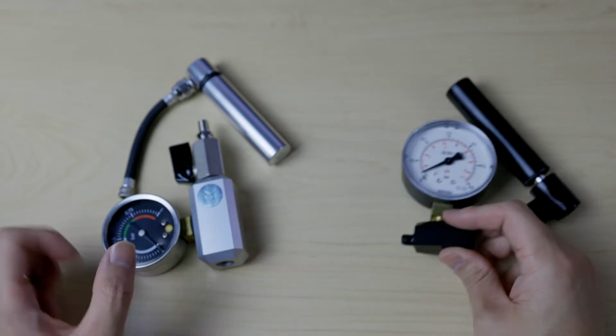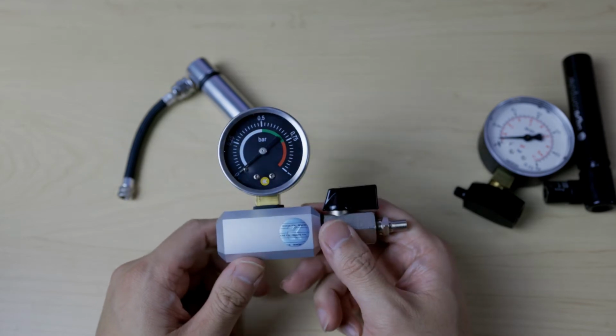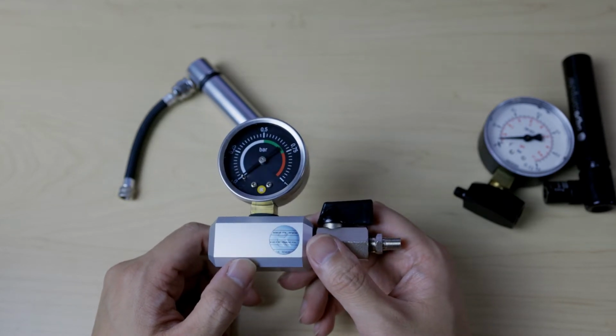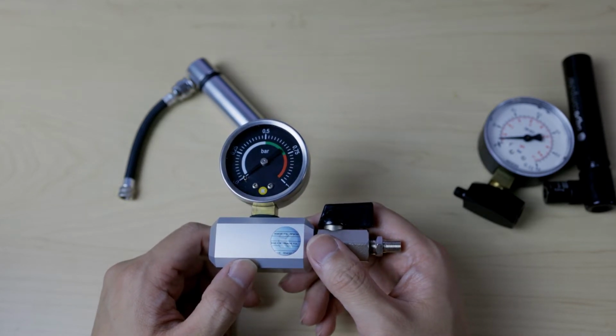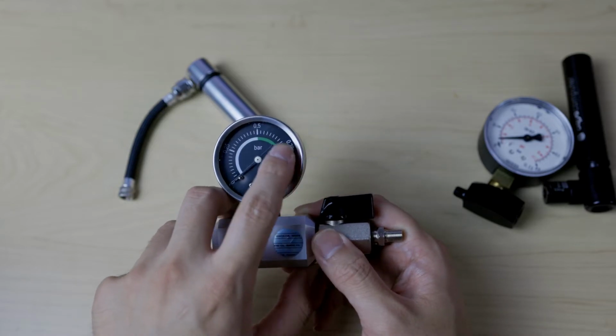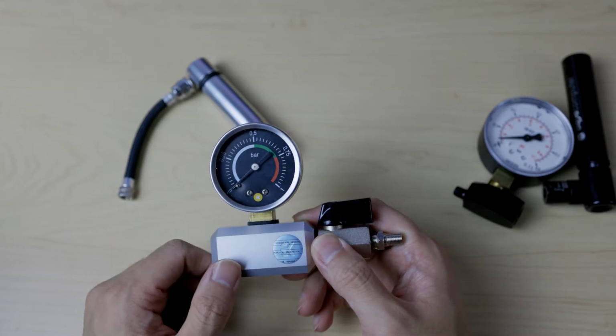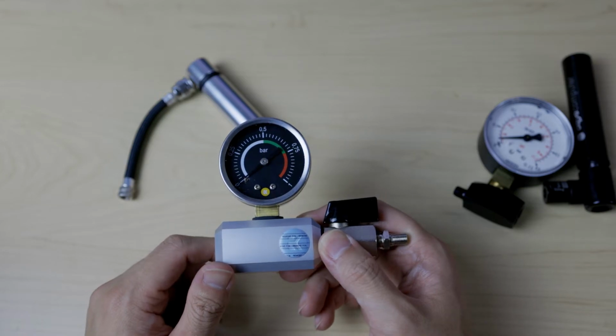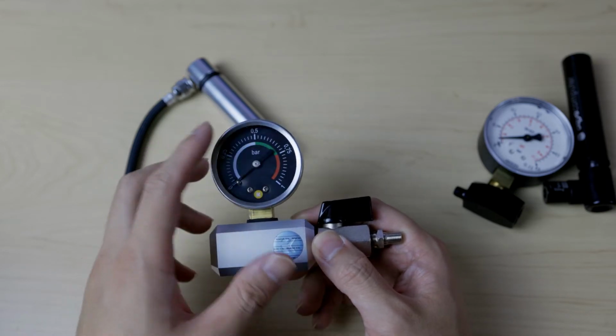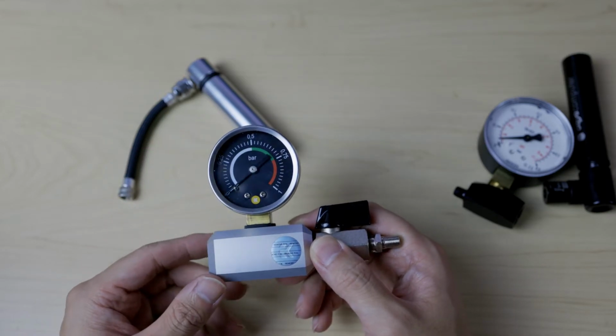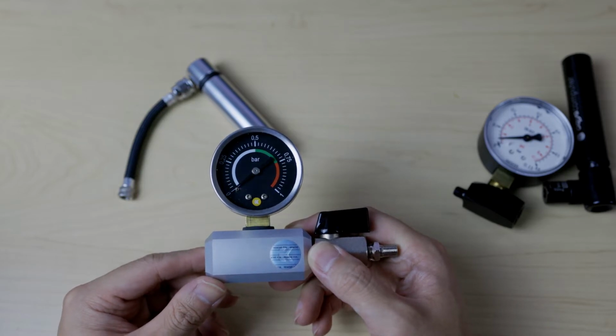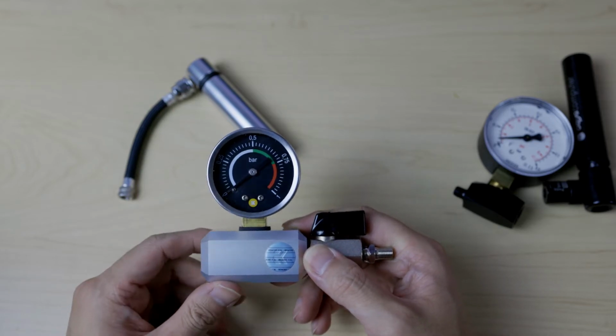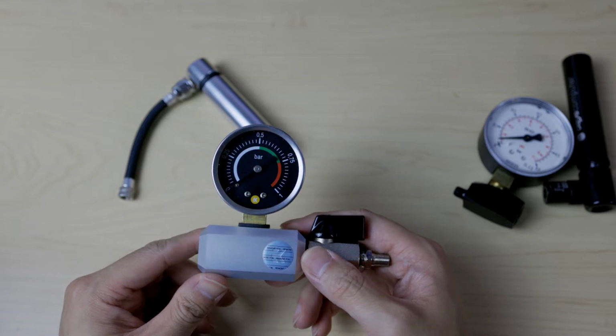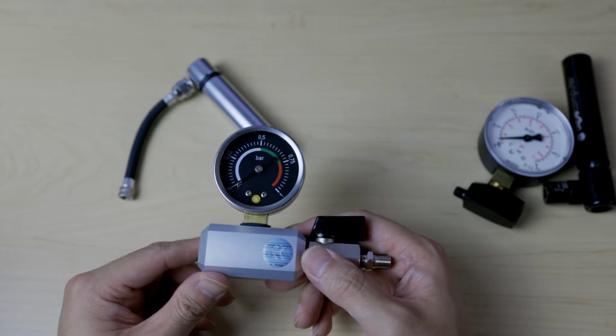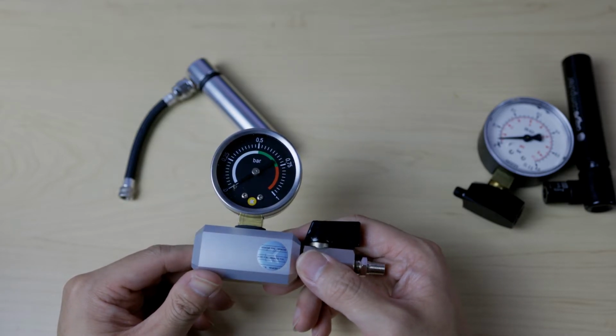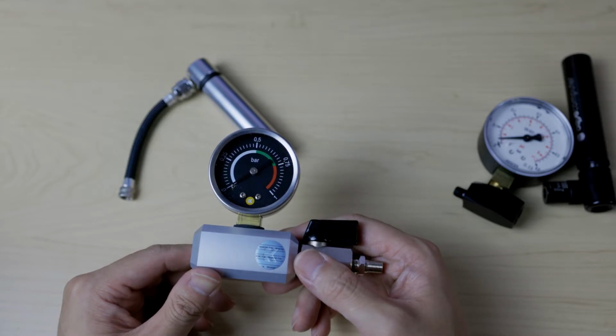What these allow you to do is test with air. If your loop is leaking, it will start dropping on the meter fairly quickly. With a bad leak it'll drop to zero within a minute or a couple of seconds; with a small leak it'll start to creep. While websites tend to say 15 minutes is enough, I think that's a little short. I'd do half an hour, that's probably a better bet.